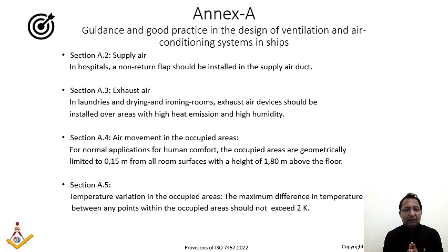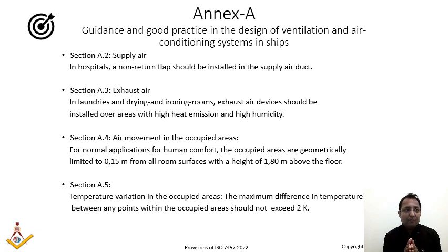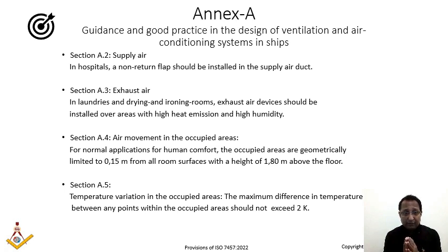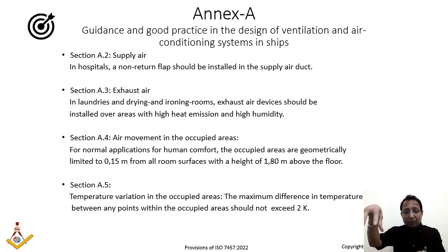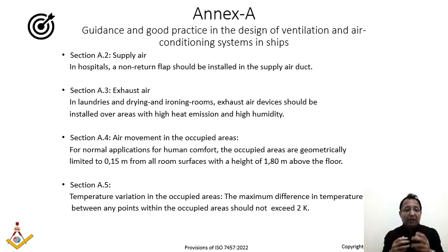Annexure A provides guidance and good practices for designing ventilation and air conditioning systems on ships. Section A.2 states that a non-return damper should be installed in the supply air duct to hospital areas, preventing contaminated air from flowing back to other rooms when the supply is shut down. For laundries and drying rooms, exhaust air devices should be positioned directly over areas of high heat emission and high humidity, such as directly above the dryer.